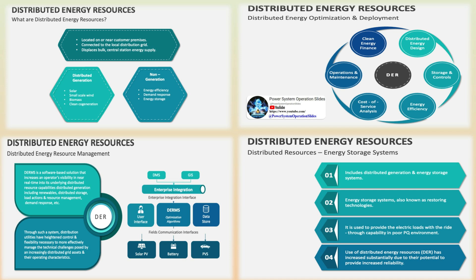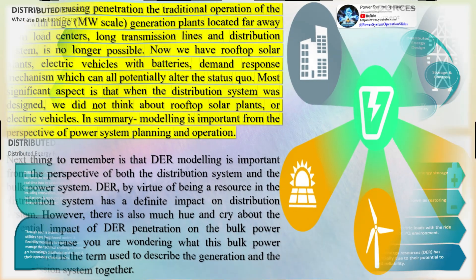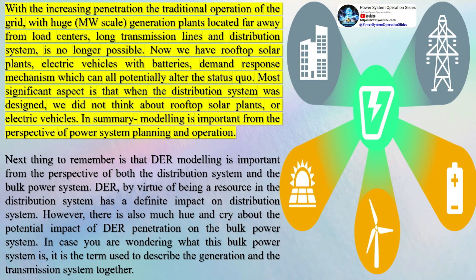Some of the potential impacts of DER on the reliability of the power system, as identified by experts, include: visibility — lack of DER data and its implications for the operation, planning, and design of the bulk power system; coordination between resources connected to the bulk power system; the effect of DER daily generation profiles on system unit commitment and ramping needs; and the effect of distribution-connected variable PV and wind output on day-ahead load forecasts.